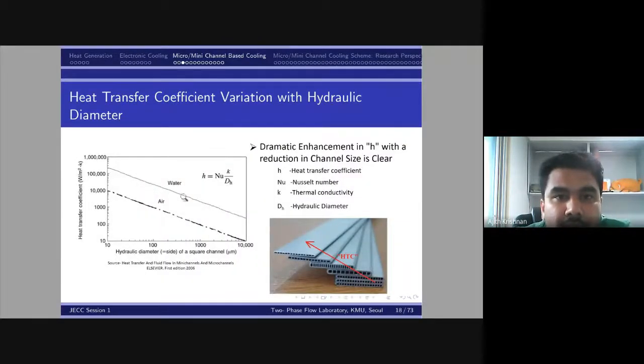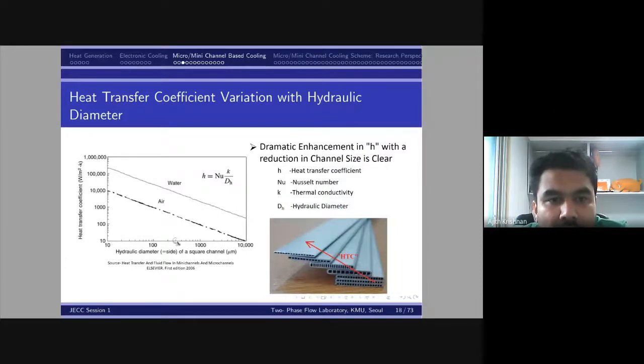This is the heat transfer coefficient variation with hydraulic diameter. If we go from a bigger channel size to a smaller one, there is a drastic increment in the heat transfer coefficient. Initially it was nearly 10 for a 10,000 unit, and later it increased to 10,000 for a 10 micron hydraulic diameter unit. So with reduction in hydraulic diameter, there is definitely an increase in heat transfer coefficient due to the increase in surface area density.